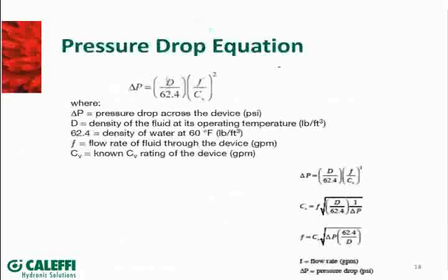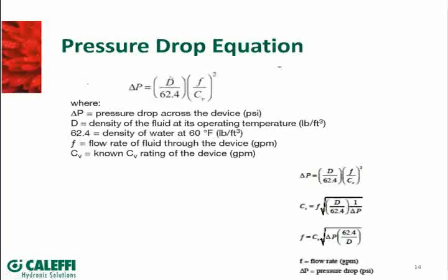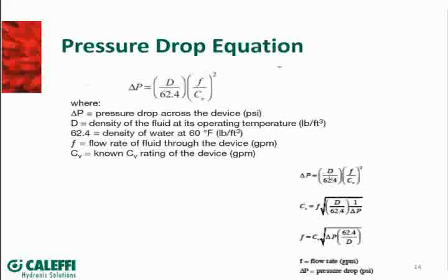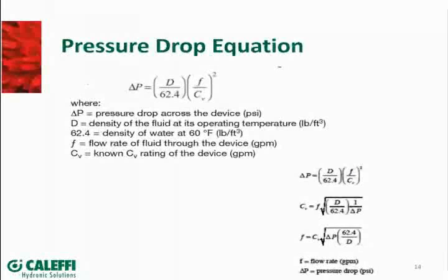Now this formula — we've pulled in another equation where we want to account for temperature. In the definition of CV, we're looking at water at 60 degrees Fahrenheit. But hydronic systems operate at higher temperatures — 140, 160, 180 degrees. There is a correction you can make for the temperature of the water. You can also use this formula to solve for different parts of the equation. If you're looking for delta P, we bring in the correction for specific gravity and can change the density of the water at different temperatures to correct for that.